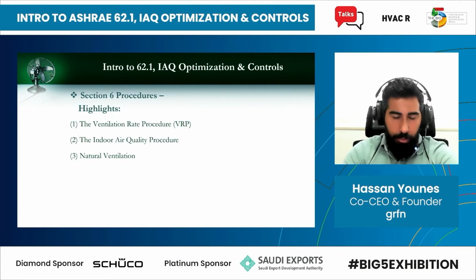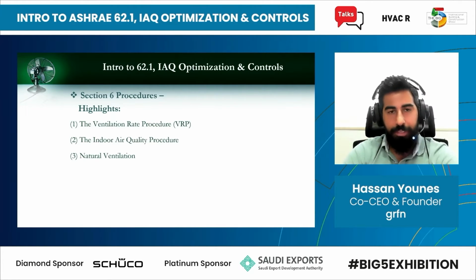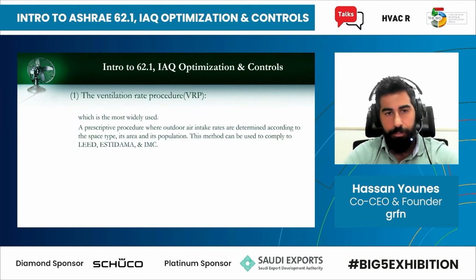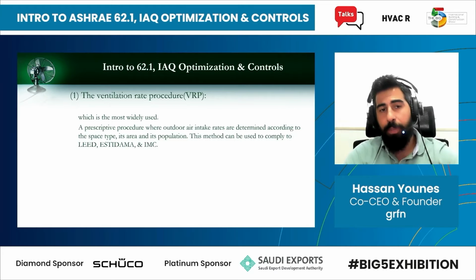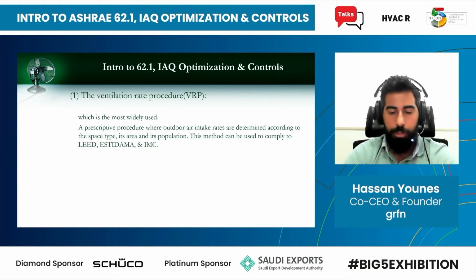Now, the most important section of the standard is probably the procedures. So we have 3 procedures to comply with the standard: the VRP, or the ventilation rate procedure, the indoor air quality procedure, and the natural ventilation. The VRP is the most widely used. This is what we normally use, let's say, to comply with the requirements from the municipalities in the UAE. With ESTIDAMA, same thing with LEED. In most cases, we use the VRP.